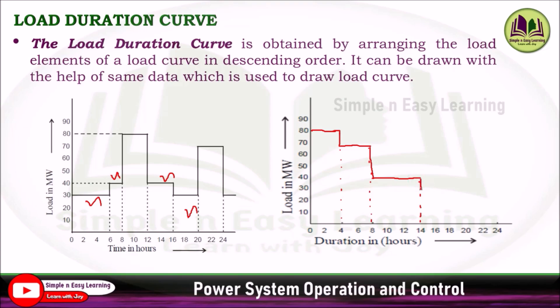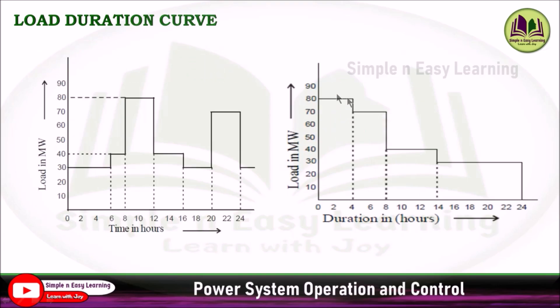The remaining 10 hours carries a load of 30 megawatt. This is how we draw the load duration curve — from maximum to minimum, in descending order: 80 megawatt, then 70, then 40, and finally 30 megawatt. The same approach can be used to draw the load duration curve for monthly and yearly curves. This completes the diagram of the load duration curve.